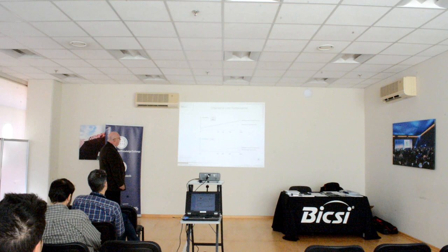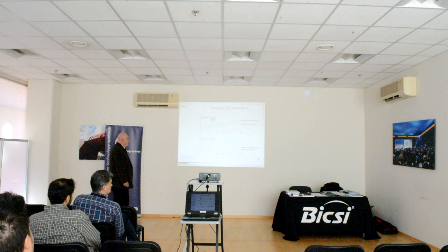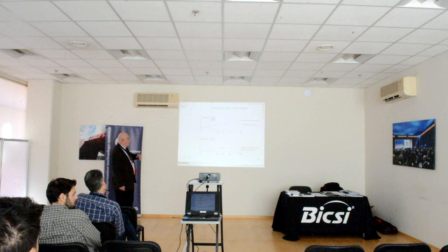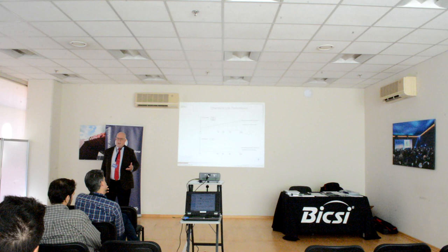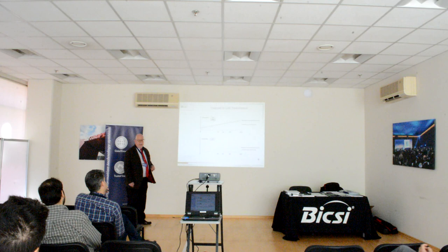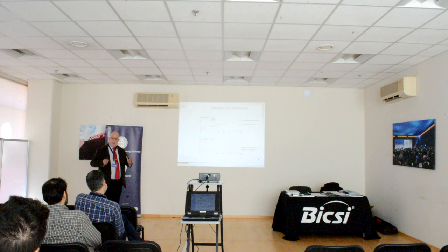Now, the problem with testing is that as these distances come down, from 2,000 metres down to the tens of metres, the maximum specified attenuation, let's say for example on multimode, which is based upon how many dBs per kilometre of fibre and then how many connections, obviously comes down also. Down to the point where when you get down to zero, then if you had such a thing as a zero length cable, you just have the expected losses of the connectors.